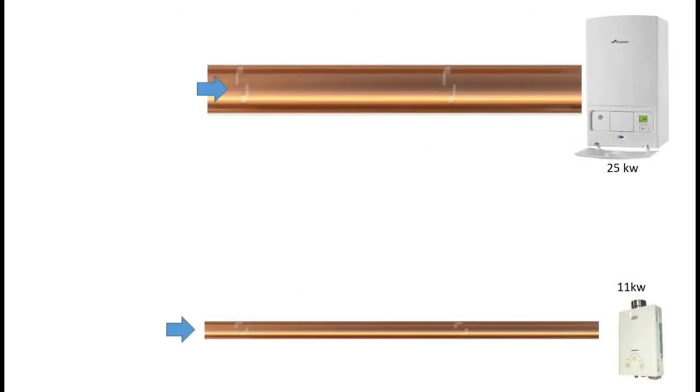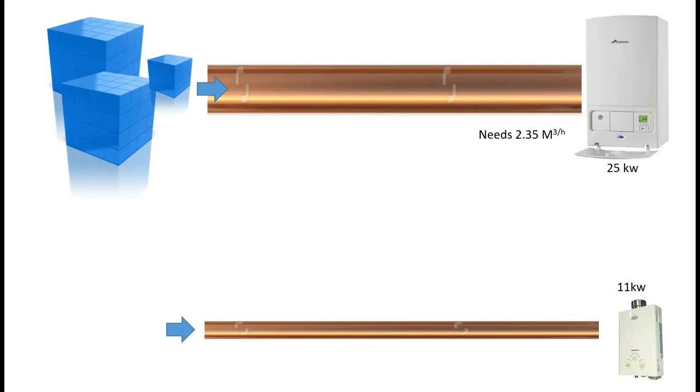Here we have a 25 kilowatt boiler and an 11 kilowatt water heater. The boiler requires 2.35 metres cubed per hour, that's 25 times 0.094, and the small water heater needs 1m³ per hour. That's 11 kilowatts times 0.094.